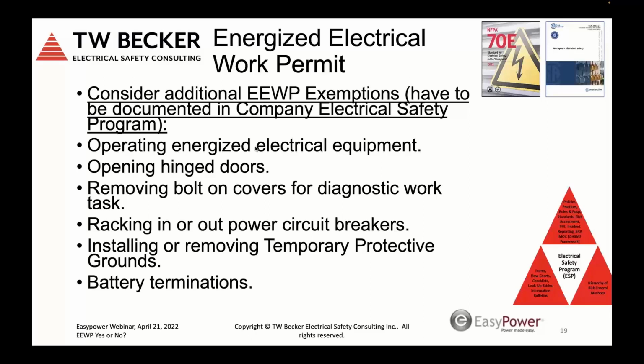How do I get to the other side to test for absence of voltage, or to test for voltage or do a load measurement? Exempt it due to equipment design. Removing bolt-on covers for diagnostic work tasks - even testing for absence - because the bolt-on cover is energized alteration. So I'm authorizing one alteration work task because there's physical alteration, the bolts and cover being removed, but we don't need a permit for that either.